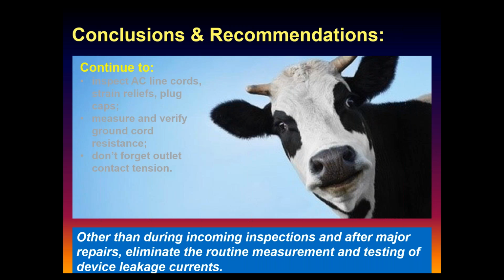I was at three different hospital systems because of all this stuff. The very first hospital, there used to be an NFPA requirement in the ER for a monthly conductive floor test - the old guys remember that - where you'd walk around with a meter and measure the resistance of the floor. This was for flammable anesthetic agents, this was like the 70s.